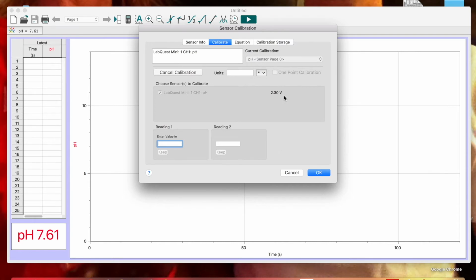So now we're going to tell the pH probe, hey, if you get a 2.30 or 2.301 voltage, it's pretty stable, that represents a pH of 4. So we're going to enter here the pH reading. It's very common to enter the voltage reading here accidentally. So now you're going to put in 4.00 and you'll tell it now keep that data point. Okay, I'll rinse and put in a pH of 10, and then we'll have this be our second calibration point.